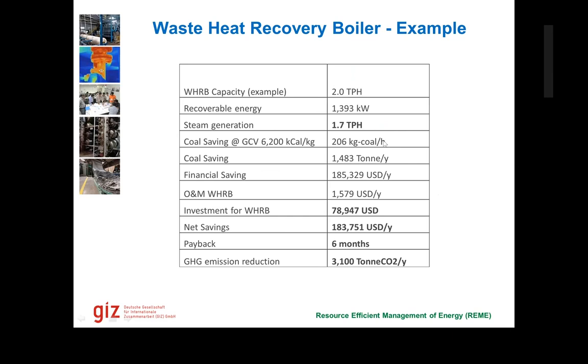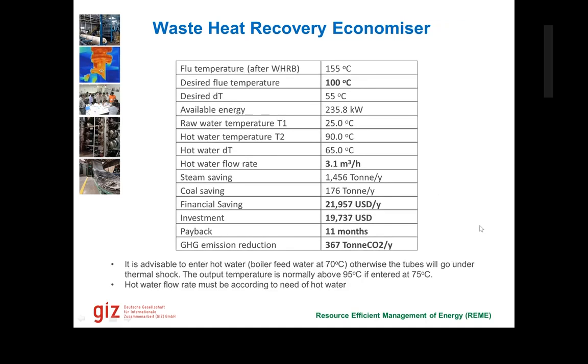A waste heat recovery boiler can also be calculated in the same way. Again, Q = m·Cp·ΔT is used everywhere in all the thermal processes. Quite similar. I think we don't need to go into details of this calculation. Very similar calculation. A big amount of greenhouse gas emission reduction can be achieved here. Normally these waste heat recovery boilers bring down the engine exhaust temperature to 150 to 160 degrees Celsius. This is still recoverable.